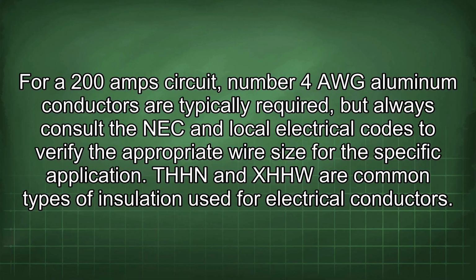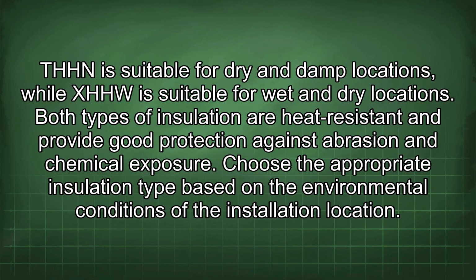THHN and XHHW are common types of insulation used for electrical conductors. THHN is suitable for dry and damp locations, while XHHW is suitable for wet and dry locations. Both types of insulation are heat resistant and provide good protection against abrasion and chemical exposure. Choose the appropriate insulation type based on the environmental conditions of the installation location.